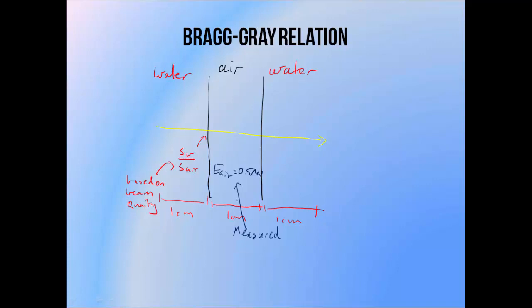For photons this is the TPR20,10, or for electrons this is the R50 value. We can use the equation to combine the measured energy in air and the stopping power ratio to give us the energy deposited in water at this point. So the energy deposited in water is equal to the energy measured in air, multiplied by the electron stopping power in water — the amount of energy lost per centimetre in water — divided by the stopping power in air.